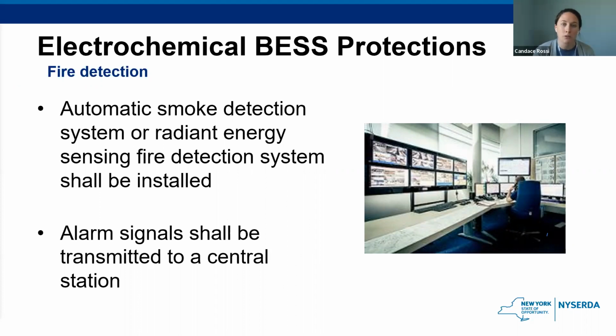So all those alarms are going to be hooked up to the battery management system, and you'll be able to monitor if there's anything going on. Central stations are used to monitor fire alarms and make notifications to the fire department at a location, sending a signal from a smoke detector or a radiant heat detector. So once again, this is just another preventative tool to ensure that the system is not going into thermal runaway, and if it is, getting the appropriate personnel there as quick as possible.